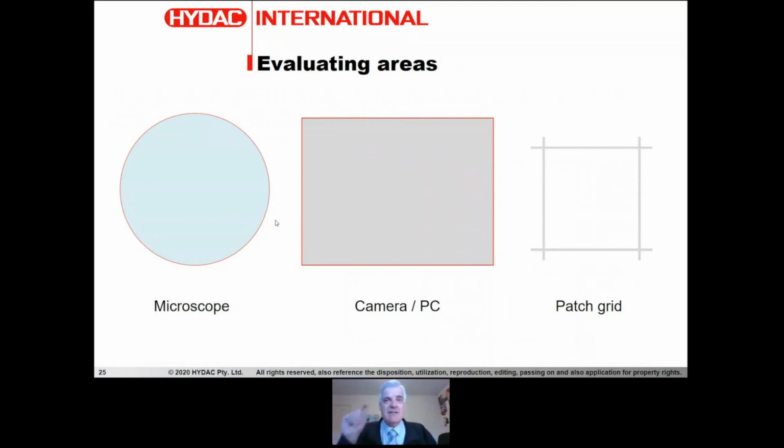You are calculating that area as a representative sample, and you count a number of areas. And what you do then is you say, look, this many areas had that many particles, therefore the patch at that area will have so many particles, and it's done by a calculation. So if you're wondering if you are going to be counting 130,000 particles, you're not. You're going to be counting an average represented area of that, and that's how that test is done.